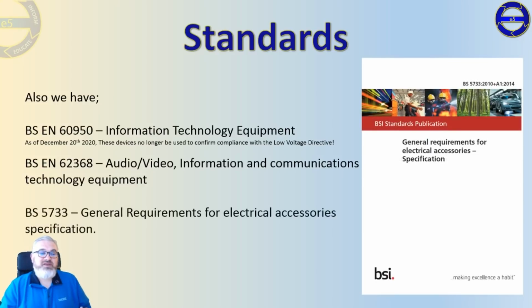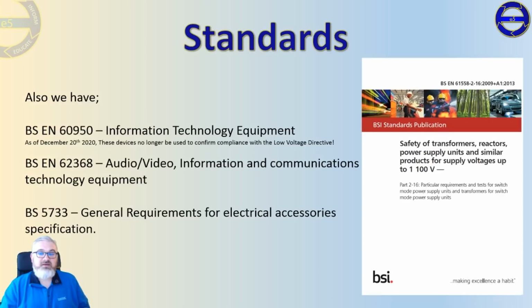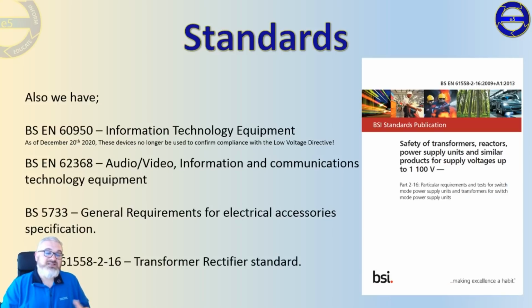Then we have BS 5733, General Requirements for Electrical Accessories - basic functional safety testing in there. But more importantly, there's another standard that covers USB socket outlets: BS EN 61558-2-16, the transformer rectifier standard, which we have in the back of 99% of all domestic sockets sold in the UK.